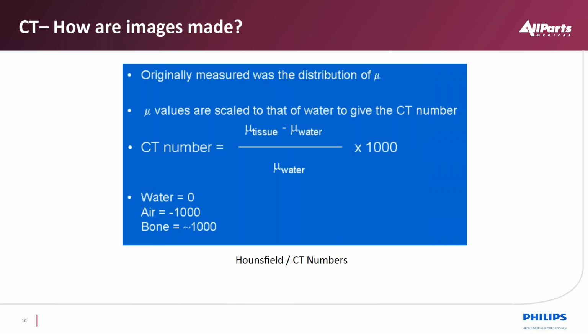So one of the things that we do in CT quite a bit, working with a physicist, is image QA. And in that image QA, Dr. Hounsfield created a scaling system. So it's known as Hounsfield numbers or CT numbers, synonymous with each other. In some documentation you'll see HU, and in other documentation you'll see CT number. They're equivalent, the same. This shows you how we derive it.